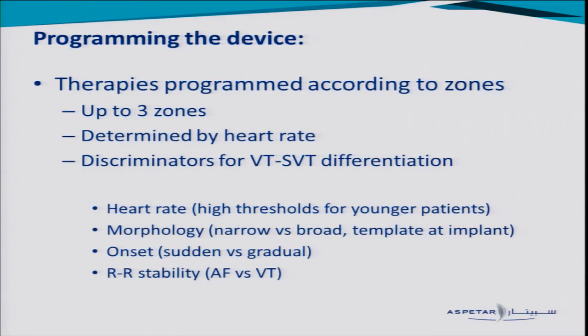The device will only do what we program it to do. We program therapies according to heart rate zones, with up to three therapeutic zones. For the patient to receive a therapy, the heart rate has to fall within one of those zones. You may ask: what happens if the athlete is training, running very fast, mounting a sinus tachycardia of 180-190 beats per minute — will they get shocked? It depends on how the device is programmed. If the therapeutic zone has a low threshold of 170 beats per minute, then yes, they're at risk of an inappropriate shock.